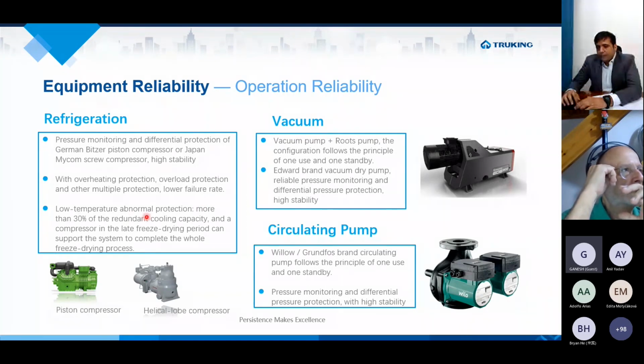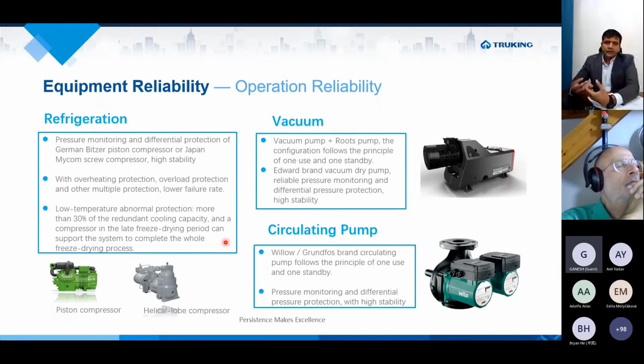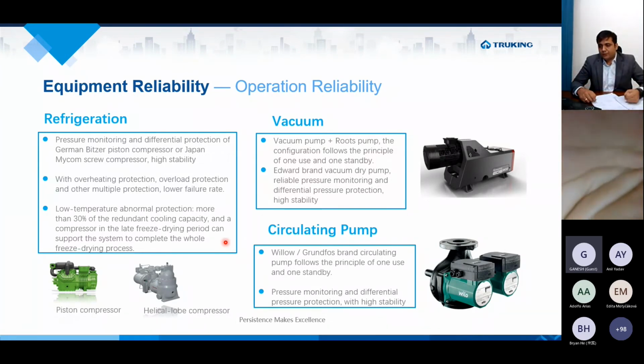Then there is low temperature and abnormal protection, and more than 30% redundant cooling capacity, and the compressor in the late freezing cycle can support completing the whole freeze drying process. Basically, we can also add redundancy in the compressor. Once primary drying has started, the load can be divided between the compressors if you have multiple compressor skids available, which ensures a lower compressor failure rate, as well as a faster reaction in terms of the performance of the equipment.